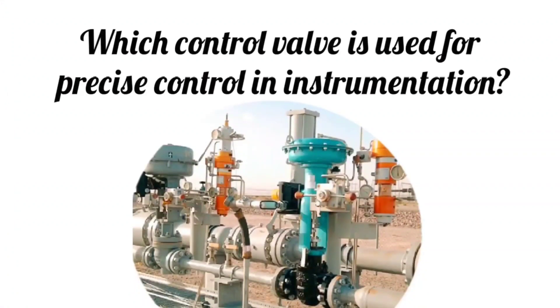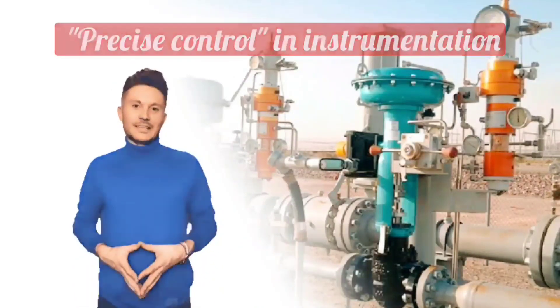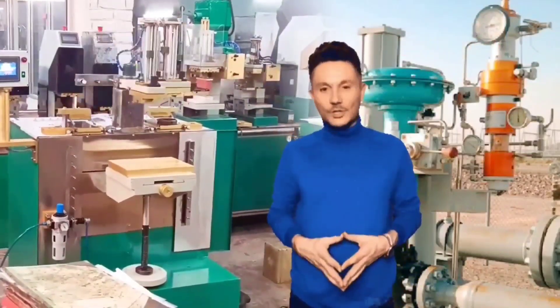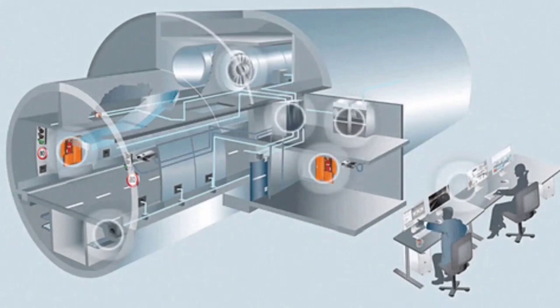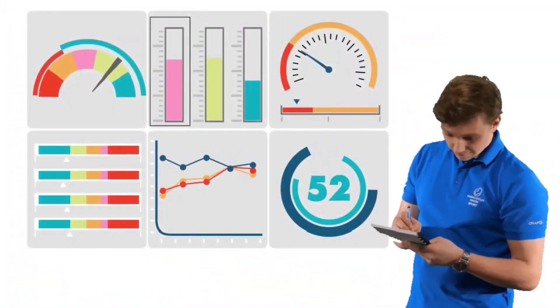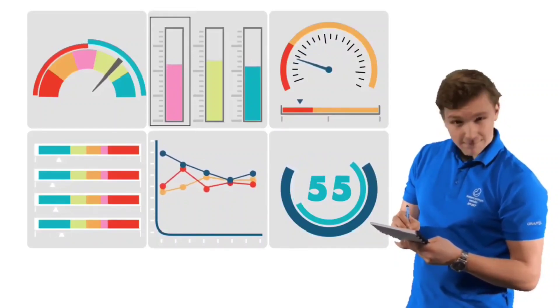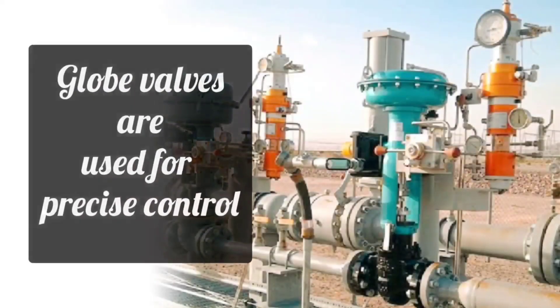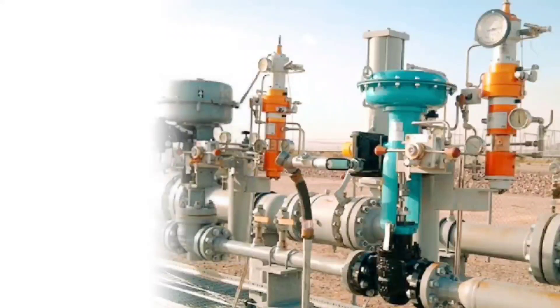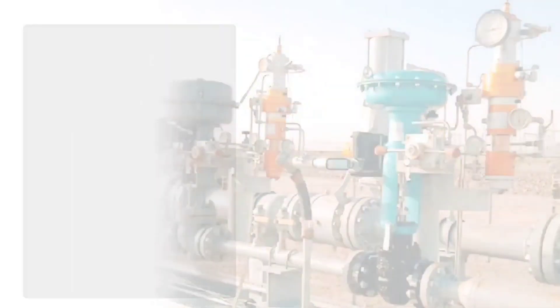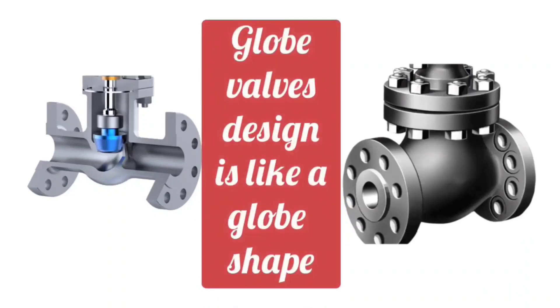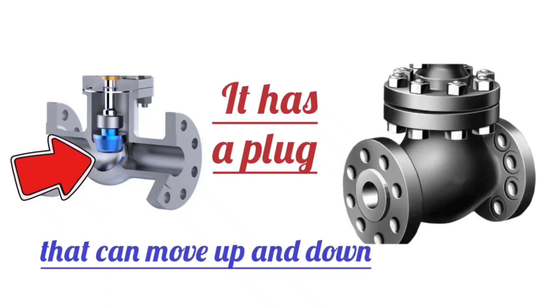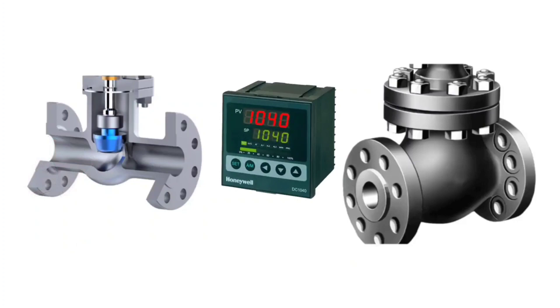Which control valve is used for precise control in instrumentation? Precise control in instrumentation means that you can control the parameters of a system very accurately and consistently. This is essential to the control system because in many industrial processes, variations of parameters such as temperature, pressure, flow rate, or level can produce significant effects in the process. Globe valves are used for precise control, and these valves are especially used in flow control applications. The design of globe valves makes them suitable for accurately regulating the flow rate. Globe valves have a globe shape design with a plug that can move up and down, and the parameters are controlled at a set point.